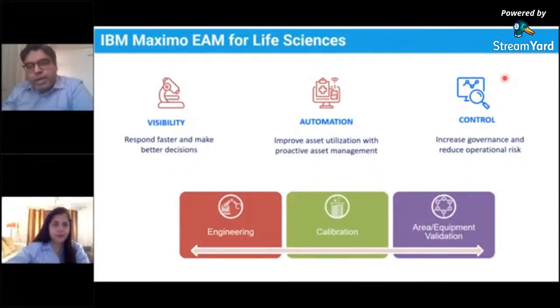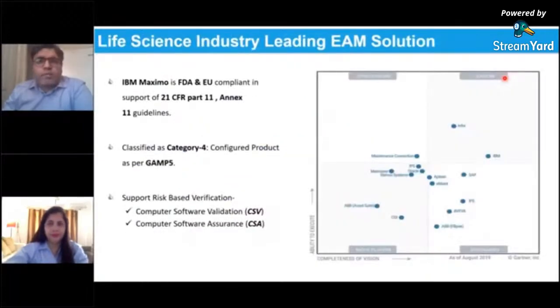IBM Maximo is used worldwide. When we talk about life sciences and pharma customers, there are three different areas where the whole maintenance happens. One is engineering, the other is calibration, and the third is area equipment validation. So Maximo gives you the ability to handle all these things and do all kinds of maintenance, which we will talk about today. Maximo is actually FDA and EU compliant. It supports the 21 CFR Part 11 and Annex 11 guidelines. If we talk about GAMP 5, it is classified as Category 4, which is a configured product.